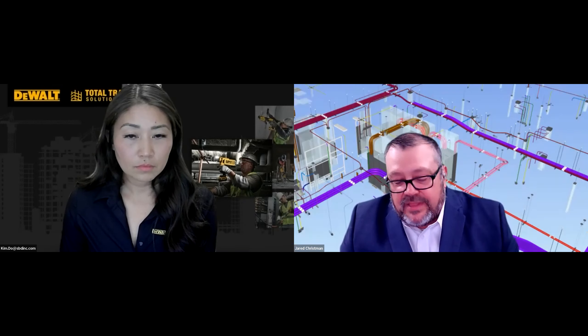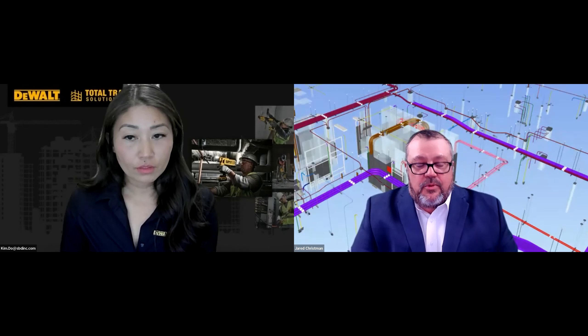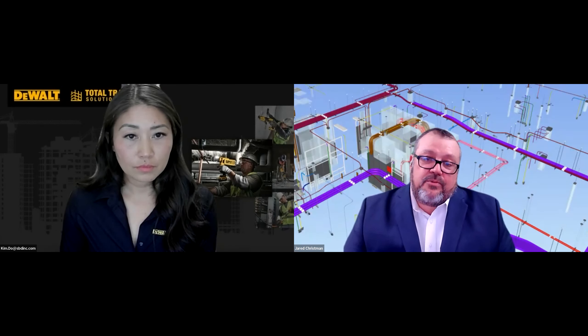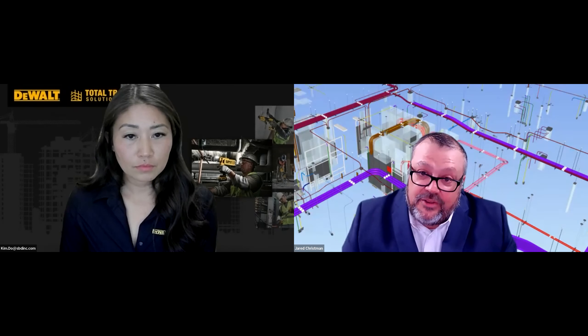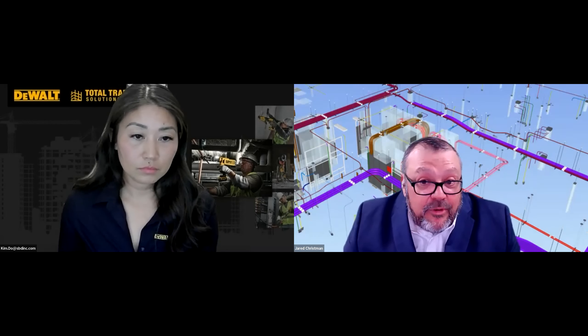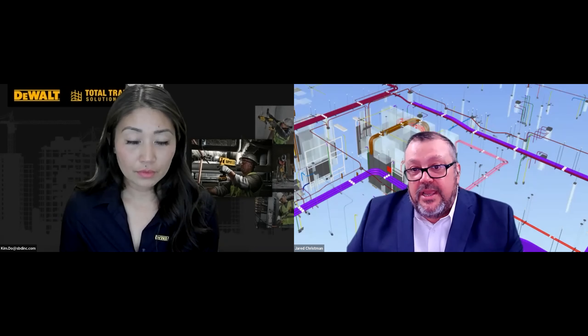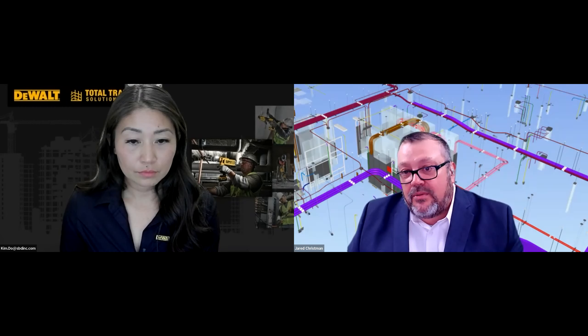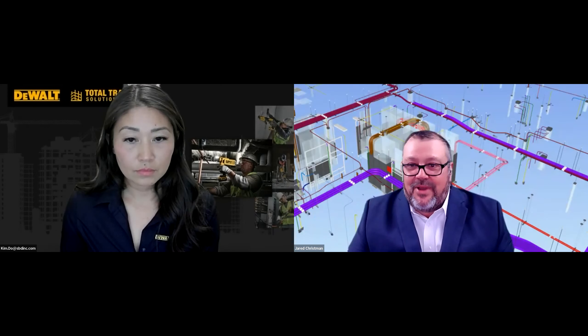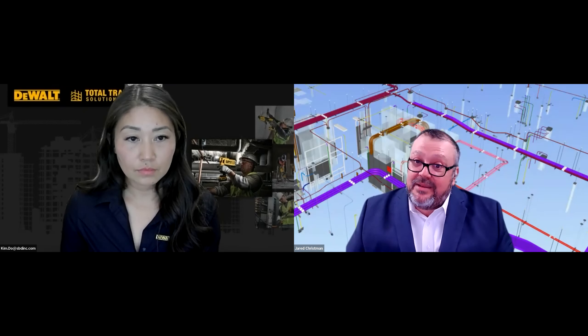Now let's talk about data in the model. Using Revit, you can export your 3D models with all your parameters. When you export and the guys in the field get it using Navisworks, they can click on a piece of pipe and it'll give them system, elevation, and circuiting information — pretty much whatever you put into Revit gets translated to the guys in the field. So you're looking at a 2D shop drawing, you have your model next to it, you click a piece of conduit in the model and it tells you if it's branch, emergency branch, or lighting — that it's 10 feet 4 inches off the floor, that it's panel LA circuits 1, 3, 5. It's got all this information embedded into that 3D object. Using 2D and 3D in tandem is absolutely the best way to get 100% of that data from the model to the guys in the field.